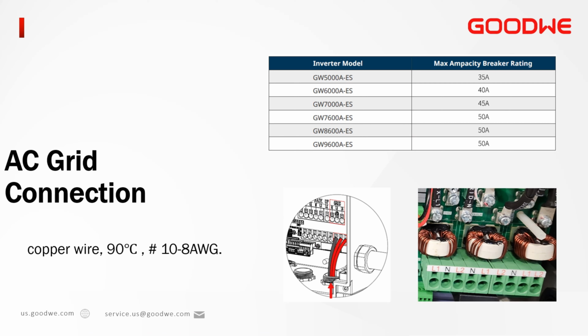Lastly, we move to the AC side. On the AC side, you will need to install an overcurrent protection device. This breaker is not included. The table on the screen is also included in the installation manual. Use it as a recommendation only because remember, the breaker is sized based on the size of the conductor that you're installing. Also, keep in mind that if you are using power limiting to prevent a main panel upgrade, the breaker will not match the table on the screen. The AC wiring terminal will accept from a number 8 to a 10.